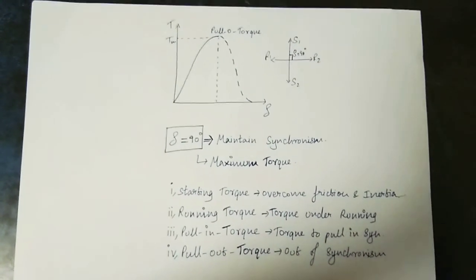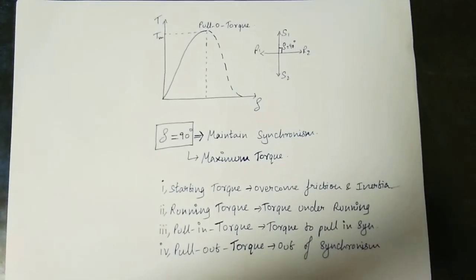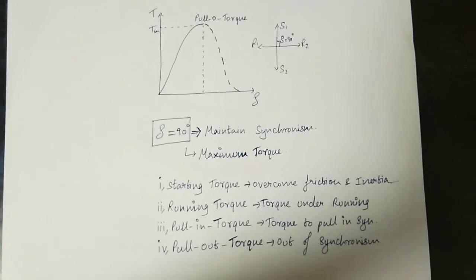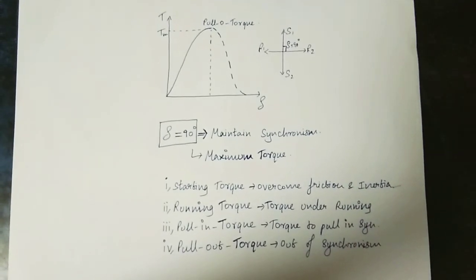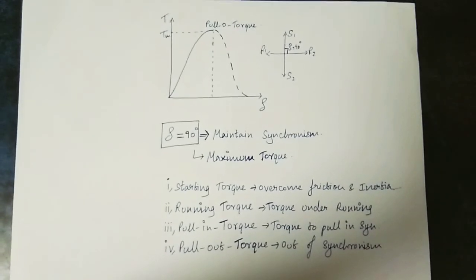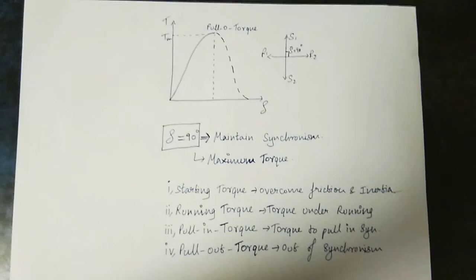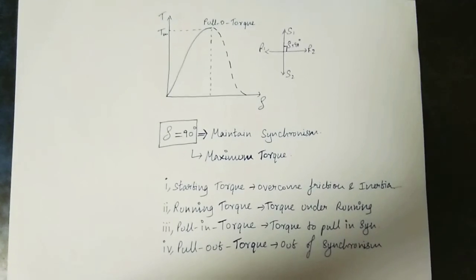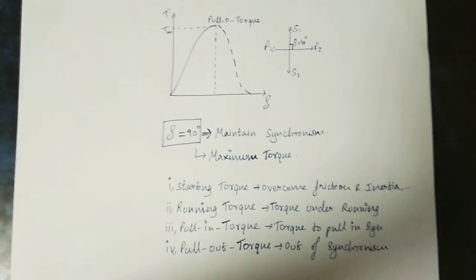Running torque is the torque developed while the motor is running under load. Pull-in torque: the synchronous motor initially starts and reaches near-synchronous speed. Starting torque increases to running torque, and then the stator magnetic field locks magnetically with the rotor — this is magnetic locking. Pull-in torque pulls the motor into synchronism at synchronous speed. Pull-out torque is the torque at which the motor comes out of synchronism.